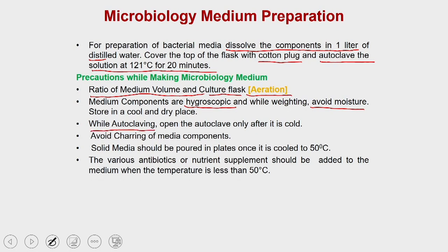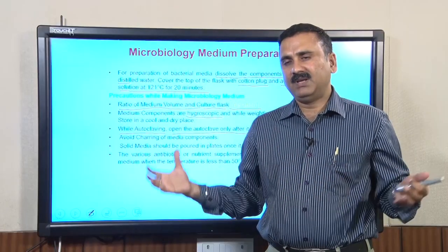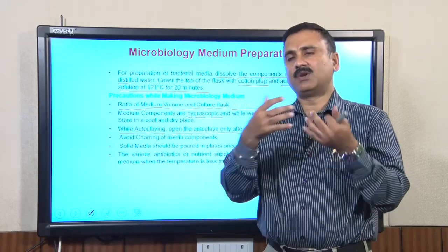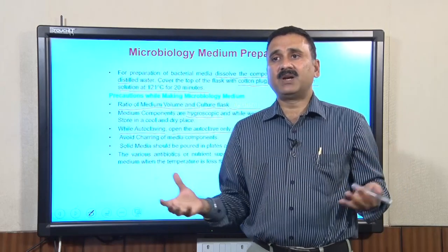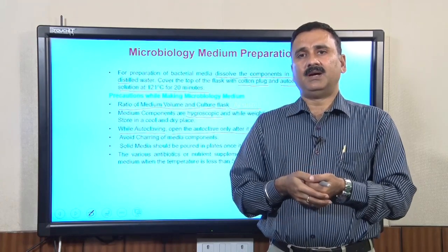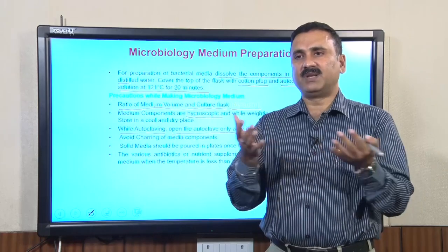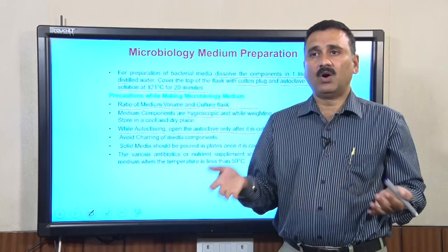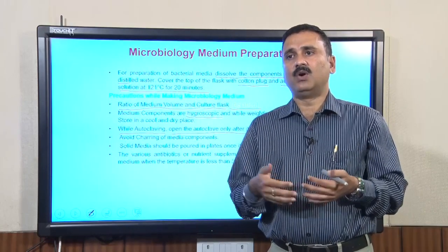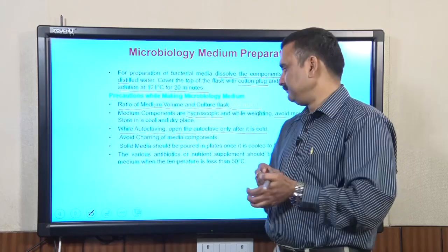You should only open the autoclave when it is completely cold, because the autoclave has built-in vapor inside. If you open the autoclave while it is hot, sometimes these vapors come onto the face. Also, sometimes when there is high pressure inside the autoclaving machine, the water present inside also comes out, and this water is very hot, so it can hurt you or cause severe burns.